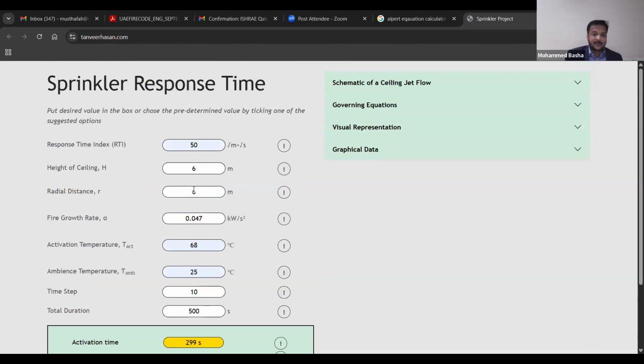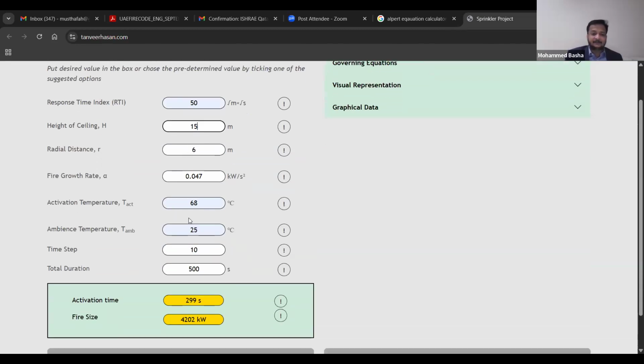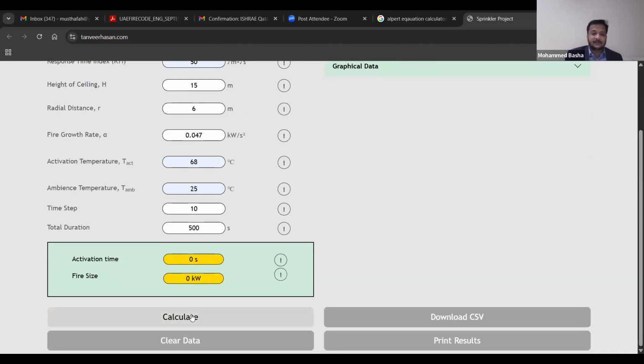Again, if I change my ceiling height to a 15-meter atrium, I need to increase the growth rate here, because it is showing 0. Maybe it will reach some value, we don't know. We will see here. Yes, it reaches at 575 seconds. You need an HRR of 15 megawatts. It's like a bus is burning. Then only can the sprinklers activate.